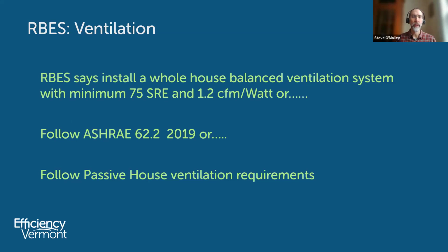I will also point out that in terms of the flow rate we need to install for our multifamily buildings, RBES historically has had, I'll call it, the prescriptive approach for the flow rate, not the efficiency of the equipment, but the flow rate. They had this simple little formula, which was 15 CFM plus 15 CFM per bedroom. So it was great. If you had a 1 bedroom apartment, you wanted to provide 30 CFM per apartment. If you had a 2 bedroom apartment, it was 45 CFM. And that still is in play. Interestingly, it doesn't spell that out in the actual code. It will show up in the handbook. And I did get confirmation from folks at the Department of Public Service that that still is a viable design strategy.